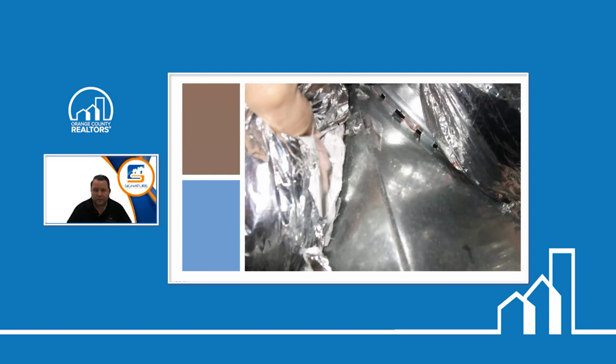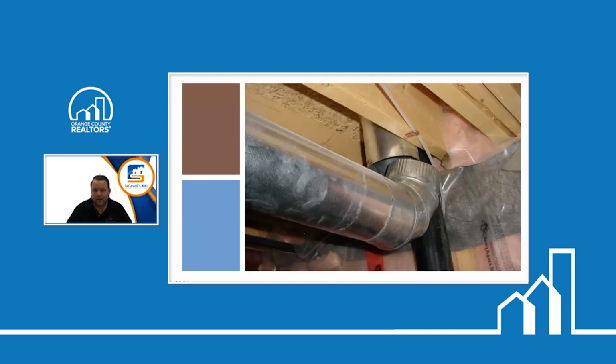Here you can see where we're pulling back the foil. This is a connection on the return, and you can see the gap here. What they should have done is glued this prior to putting the ducting in. You've got to disconnect the duct here. Again, that's just something you really have to pay attention to.